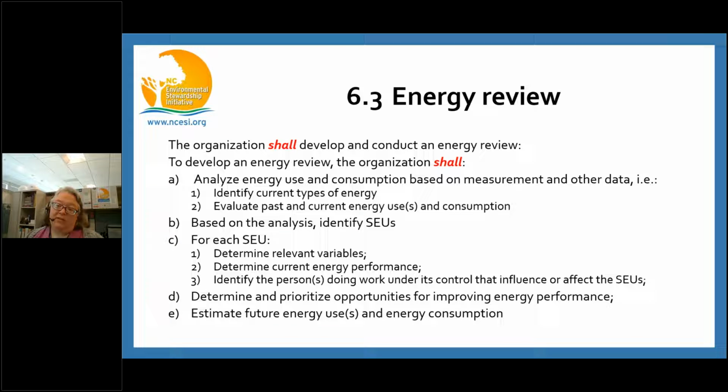For each significant energy user, then you need to figure out what changes can affect your energy usage for that specific user. So for example, heating degree days or cooling degree days, maybe your average outside temperature or humidity, your working hours or occupancy, production output, anything like that. You might want to see what effects those have on the energy usage that you are tracking. And then from these, you can determine what's measured, what can be measured, its current performance, and who has control over the device, including your contractors.